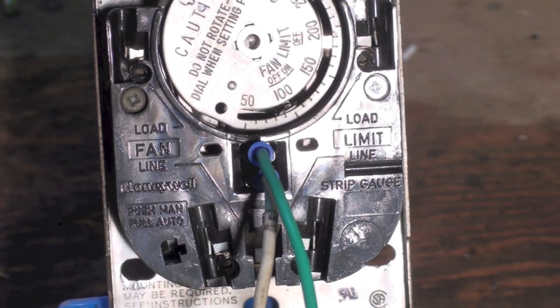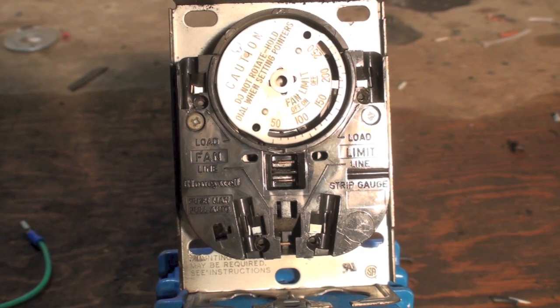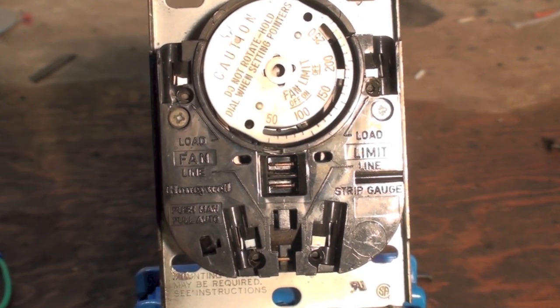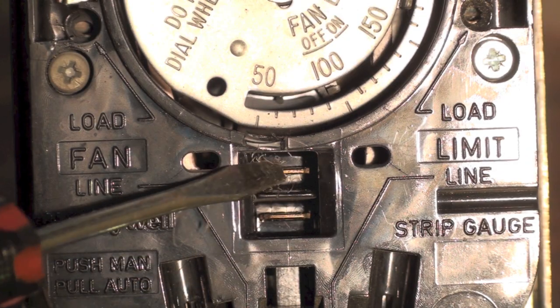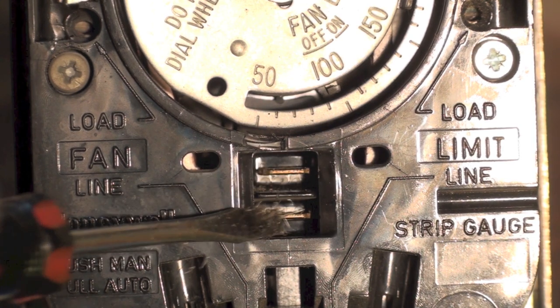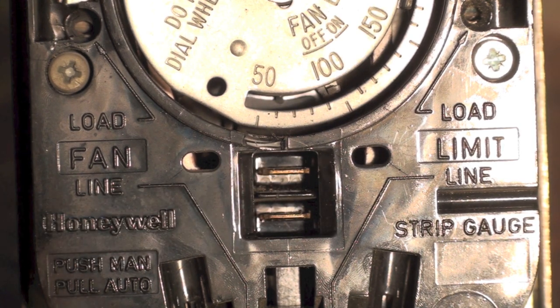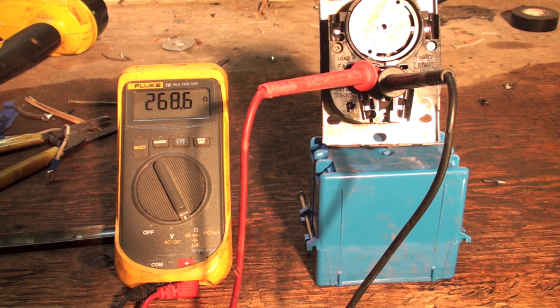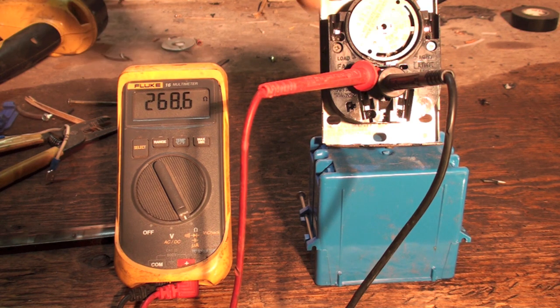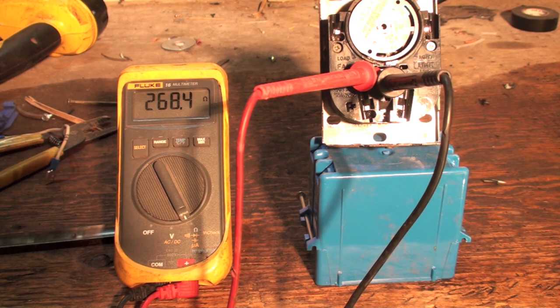Okay, the wires are taken off and you can see these two terminals right there. Those go to a heater. What I've done is put an ohmmeter across those two terminals, and you notice I'm reading 268 ohms.